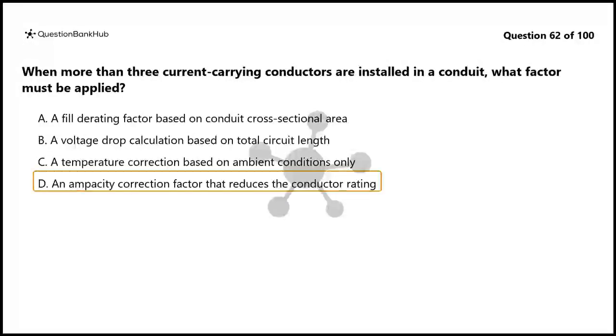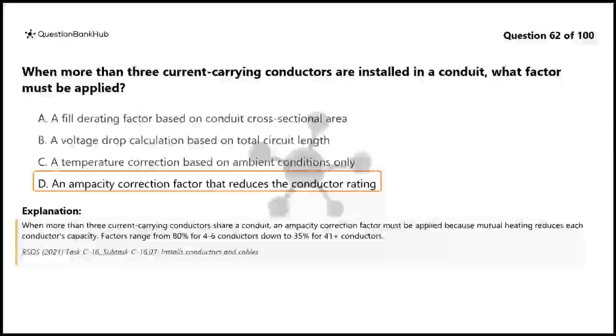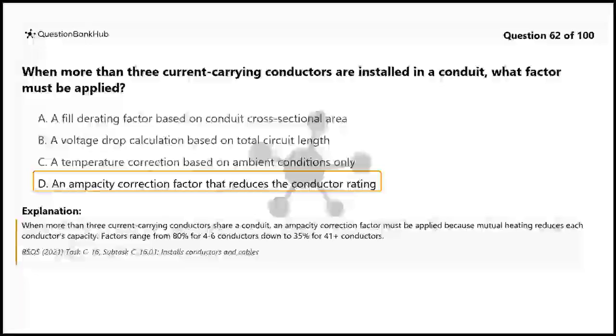The correct answer is D. An ampacity correction factor that reduces the conductor rating. When more than 3 current-carrying conductors share a conduit, an ampacity correction factor must be applied because mutual heating reduces each conductor's capacity. Factors range from 80% for 4 to 6 conductors down to 35% for 41 plus conductors.